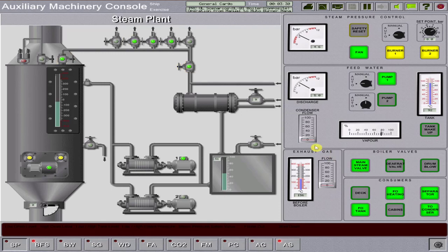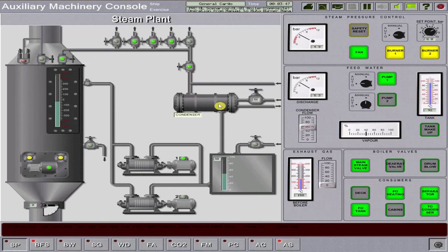Open cooling to your condenser by adjusting the condenser flow control valve, so that excess steam will be converted back to water going back to the condenser tank, otherwise known as the cascade tank.